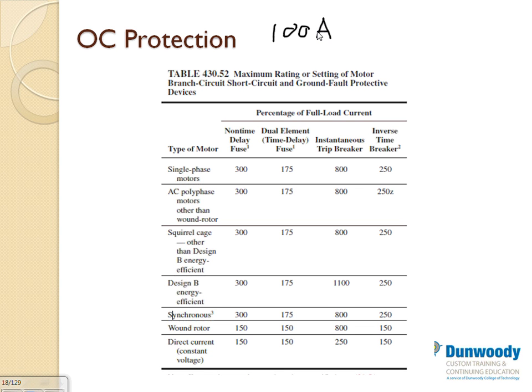Most of the time, for smaller motors, you're going to be in this area, with this type of circuit breaker. A dual element time delay fuse is a good application. So let's size it based on all of them. For that motor, based on this one, you multiply by 300. That will give you 300 amps. Does that make sense? That will give you a 300 amp non-time delay fuse. If it's a time delay fuse, your fuse is going to be 175 amps. And I want to leave the inverse type for the end. If you're using a circuit breaker, you're going to have a 250 amp circuit breaker.